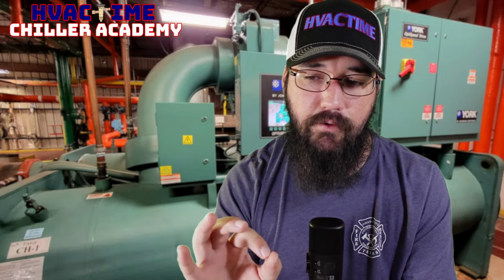Now, this is for proper charge. Now, here's something I'll throw out. Okay, this just clicked. Maybe this is causing some of the confusion. I don't know. You can tell me. Where this gets screwy is if you're undercharged and you're not maintaining proper refrigerant levels because you don't have enough refrigerant in the first place to maintain those levels, then you'll see what you're seeing. You'll see your subcooling drop. You'll see lower liquid levels in the condenser because of charge.